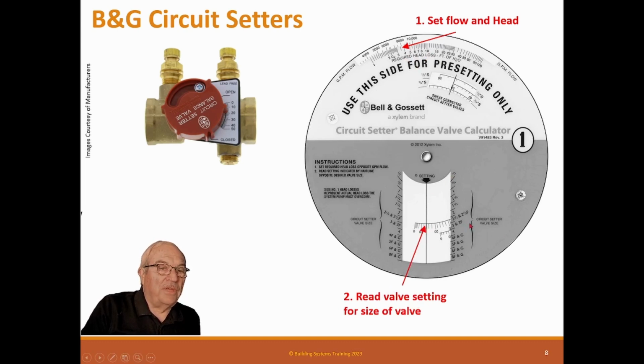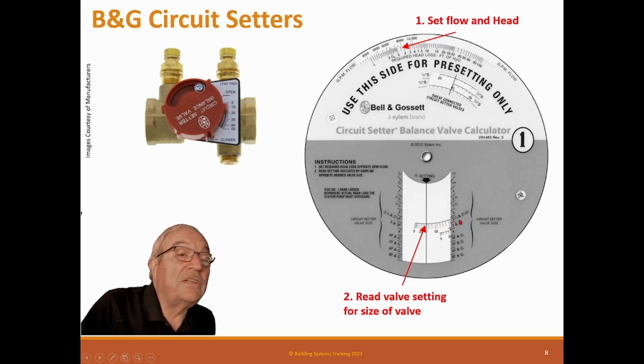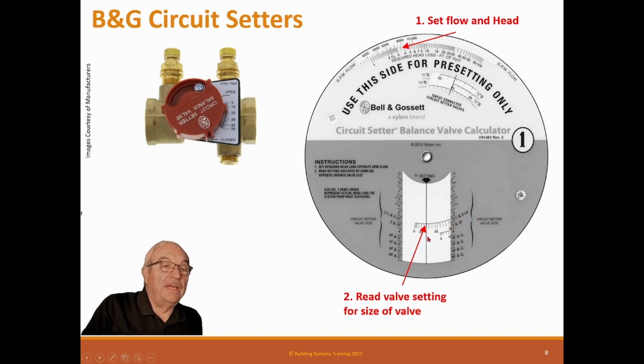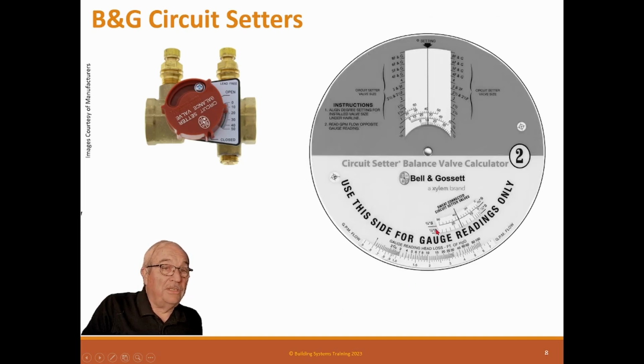So if you have a 2-inch here, I think it's 1.5 inches. I can't see that very well from here, 1.5 inch valve. And where that line is where it should be adjusted to. To get this flow at this head, you need to adjust the valve to there, which is fine. But normally we don't know that, right? So we need to use side two.